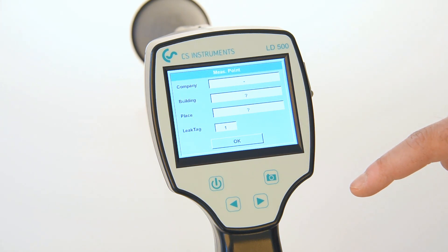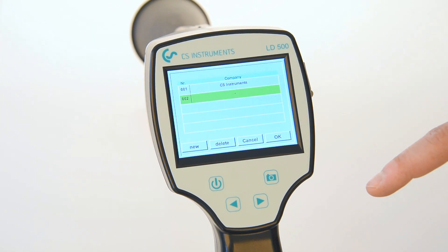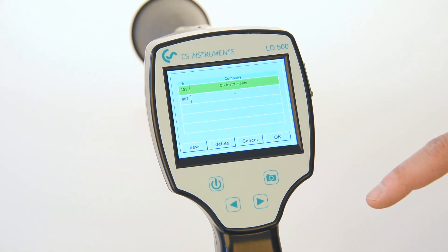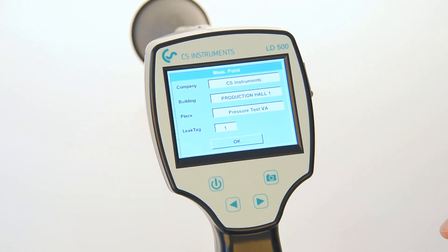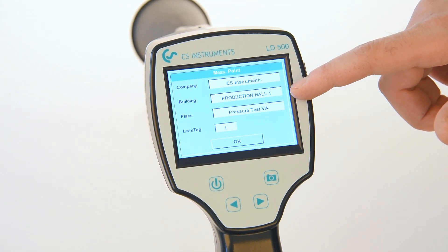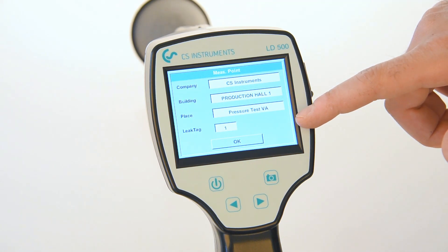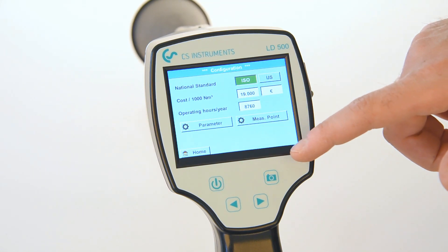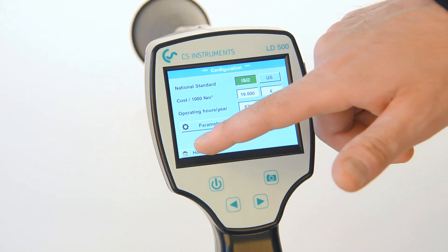In order to simplify the repair and description of each leak, individual information for each leak can be saved into the instrument. Company name, building name, and leak location can be described in great detail, making it easy for the repair team to locate each described leak. The leak counter can also be set individually. After everything is set up correctly, the user can start with the leak audit.